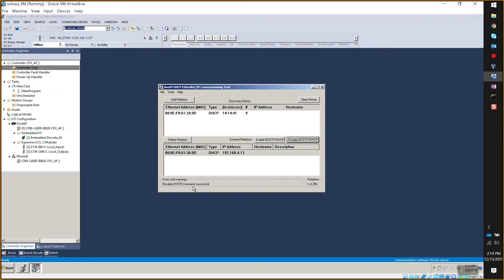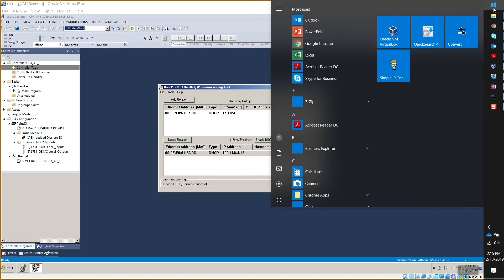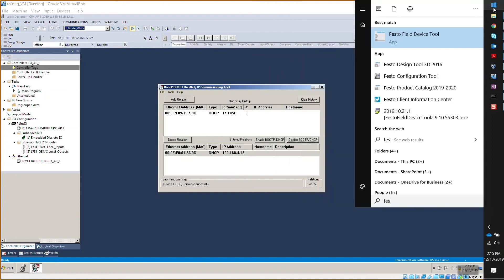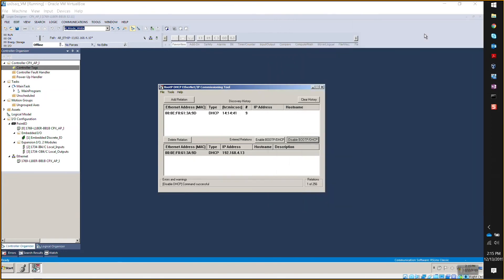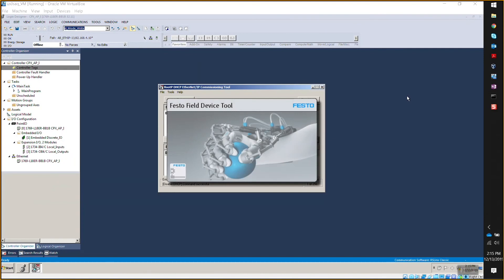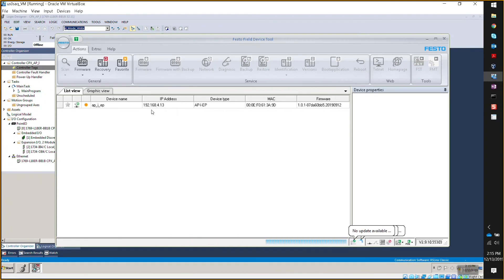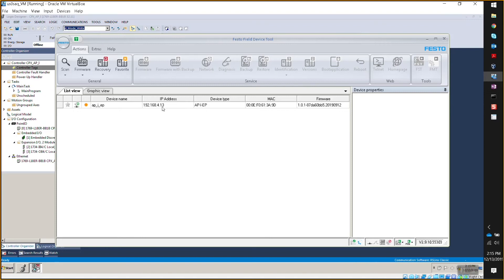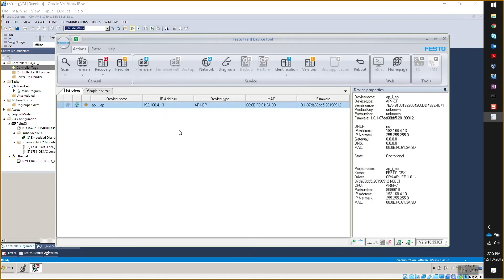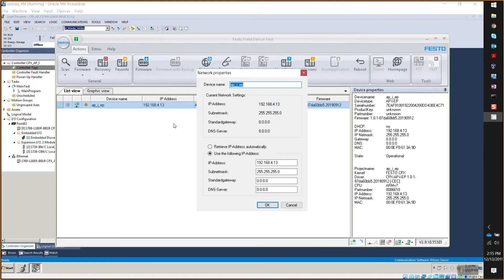You can check it different ways. You could even check it with our FDT tool. So FDT is Festo field device tool. This one, right? Yeah. Okay. So that would be one way. And then the other way would be just to ping it with a command prompt or something like that. There it is. So 4.13. If you want to be double sure, you could always turn it off, turn it back on again to see if it comes up with the same IP address now. Or else if you just click on this, or maybe it's right click and go to network. There it is. And it says it's going to use the following IP address. Yes. So it looks like it's static for me. So I think you're good.